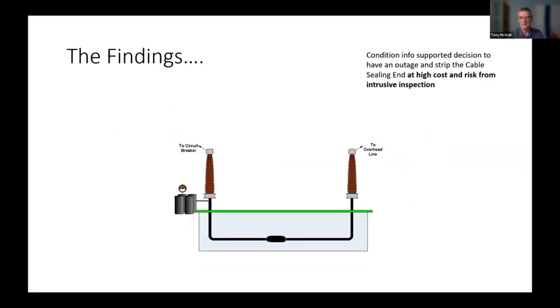So we decided to take the cable out. And I must thank Carl Johnston, a colleague at National Grid many years ago, who's continued in this field, as he was the one who was involved with this mostly. And taking a sealing end out, taking it apart is a high-cost job. You're taking the cable out of service. You've got to do the oil management. You've got to do the safety. You've got to do the site supervision. It's a high-risk thing because it's intrusive and you can damage the cable. So it's not something to be taken lightly. And as a consequence of finding partial discharge and high gas, we went in.